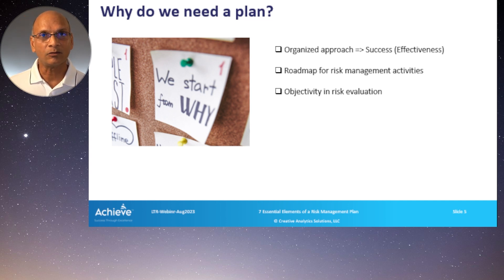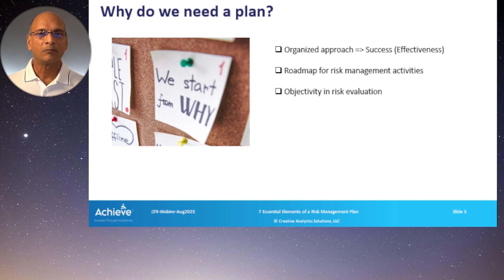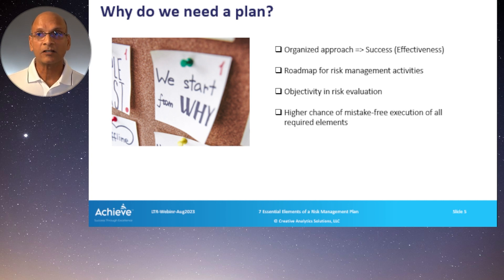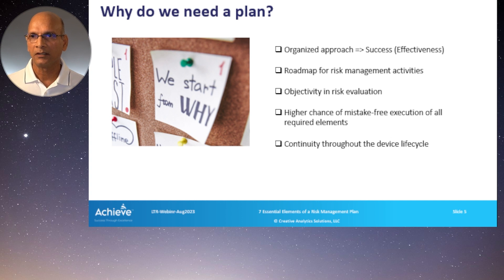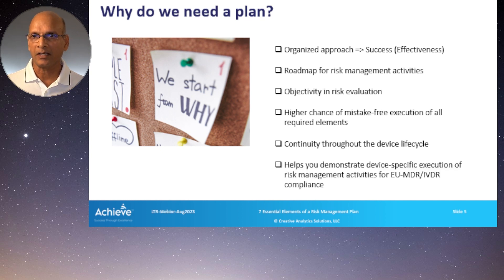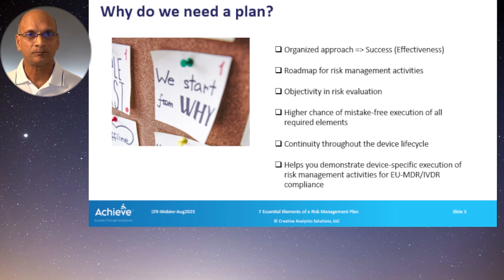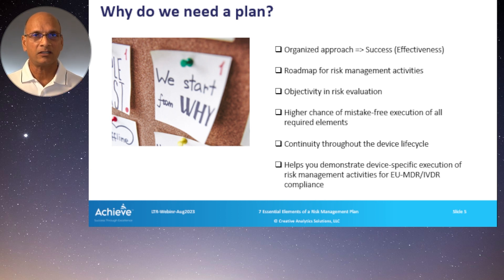Along the way, we may find that we don't meet the criteria, but the rules remain the same — rules should be set up front. There are higher chances of mistake-free execution for all required elements because everybody will know what is supposed to be done and the right people are doing the work. It ensures continuity throughout the device lifecycle, since in post-market you might have many design changes that should become part of your plan. Further, it helps you demonstrate device-specific execution of risk management activities for EU MDR and IVDR compliance — this is your device-specific execution showing that you have worked within the 14971 framework for a particular product.